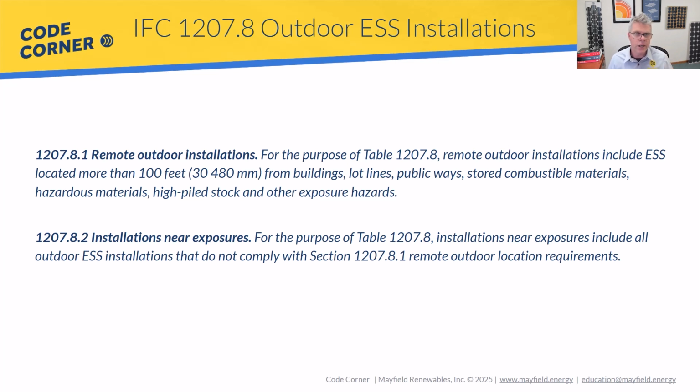If we are going to consider our installation a remote location, we have to be more than 100 feet from buildings, lot lines, public ways, these hazards, these potential things that could, if there was a fire specifically, catch on fire, or things like lot lines or buildings or other things where people may be congregating.